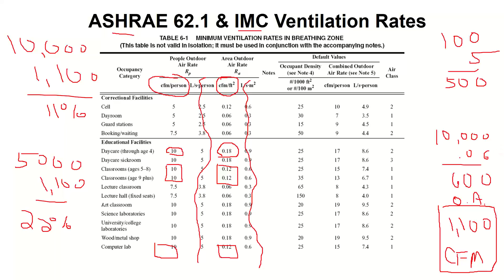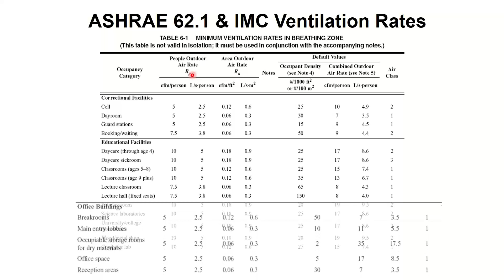Elijah says the minimum OA rate should be RA plus RP. Yes, correct. So what he's talking about is RA right here and RP right here. You add the two of them together, and that becomes your minimum ventilation, meaning that is the legal code minimum. You cannot bring in any less air by law and be okay. You could bring in more. You're allowed to do more, but you can't do less.